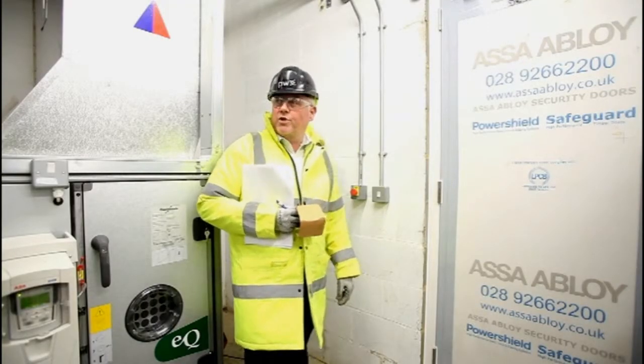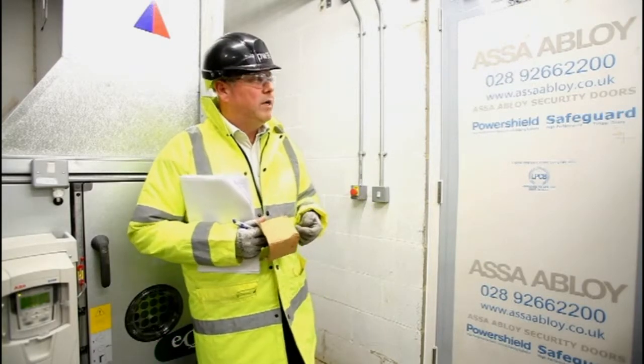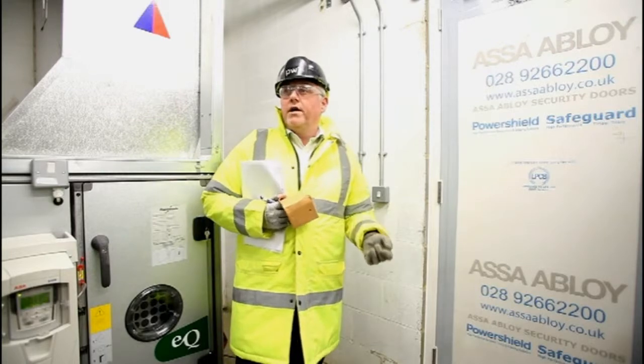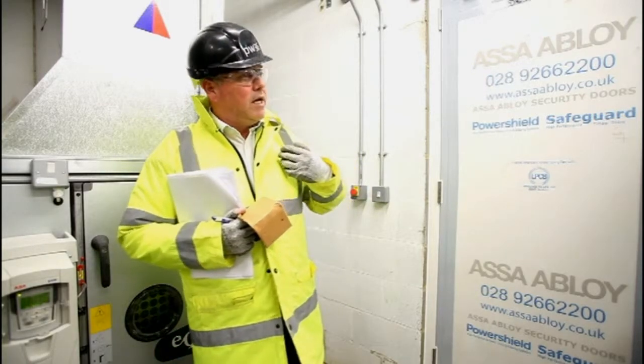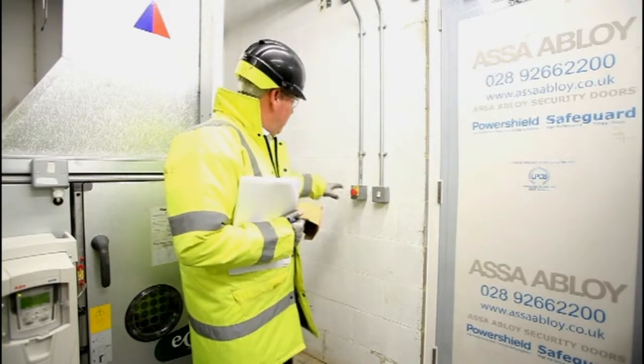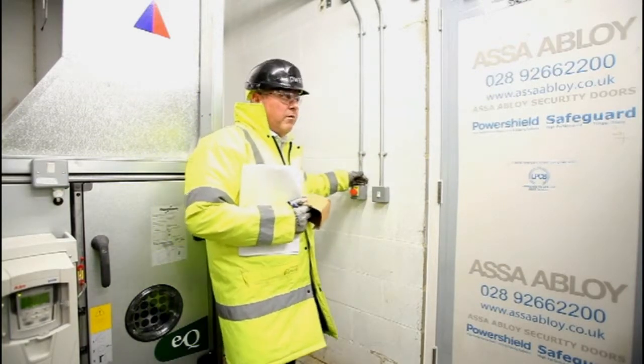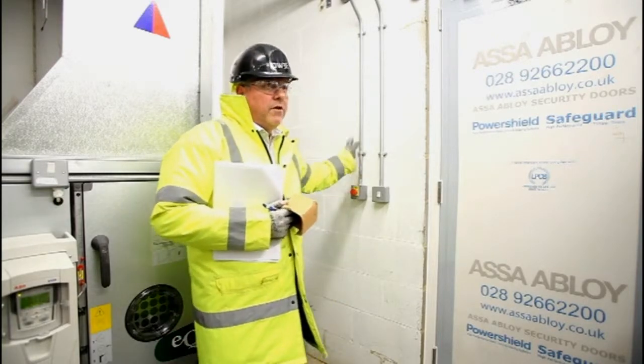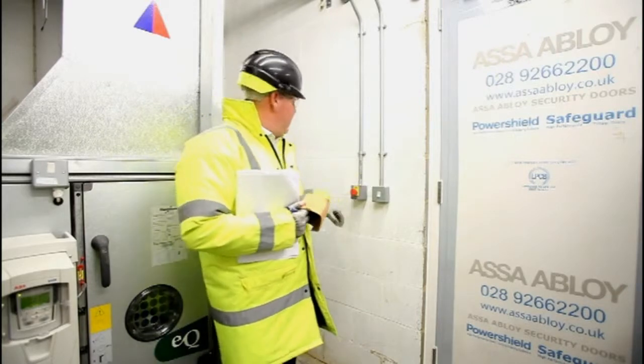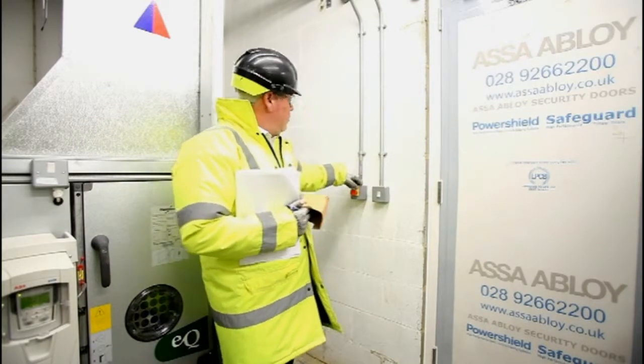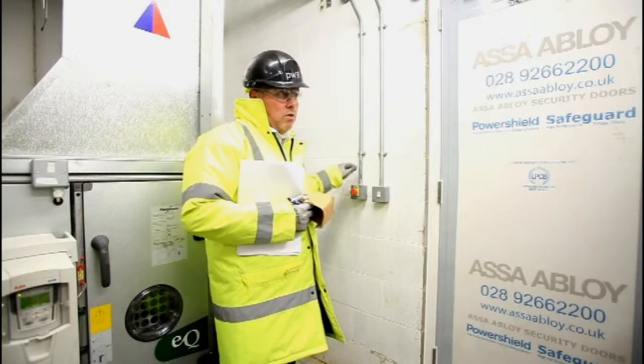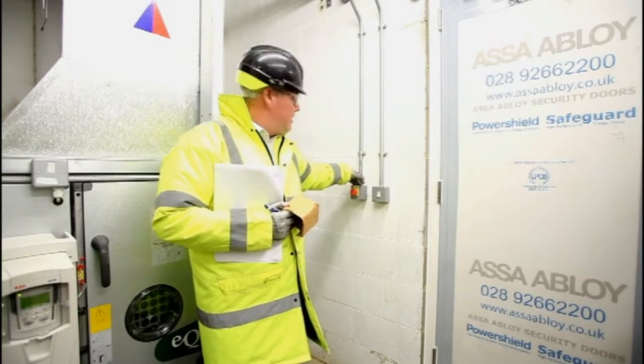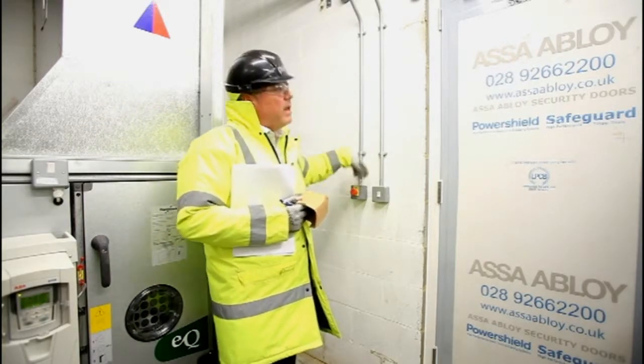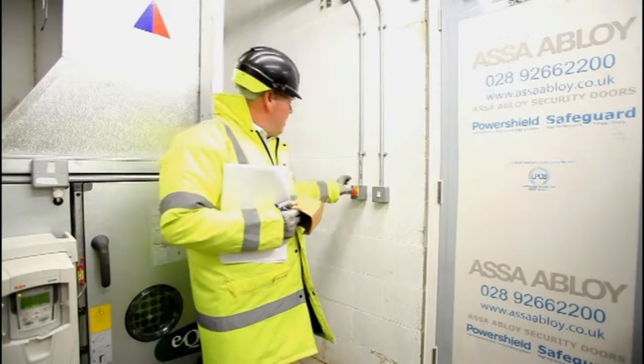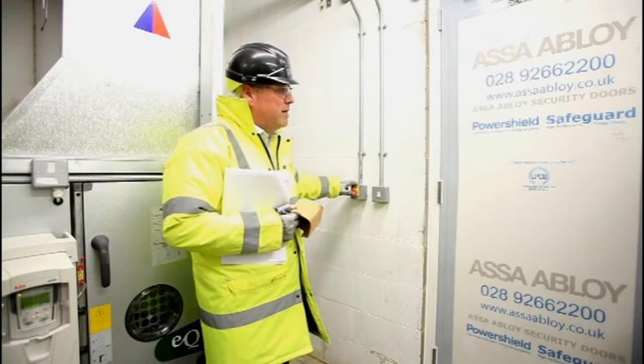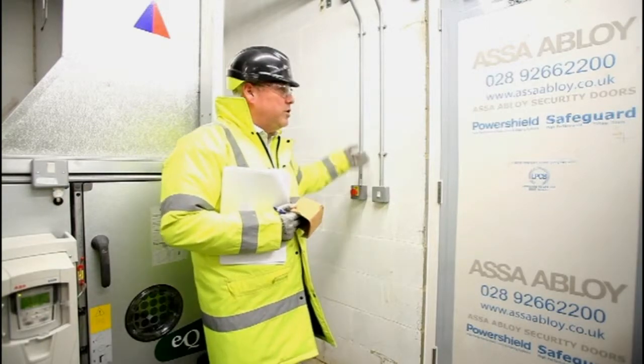There are several safety interlocks within the system that turn the system off should there be an issue. Should anybody be in the plant rooms and something become apparent, for instance there's a major leak or there's a fire, anything else, as you leave the plant room we have what we call an emergency knock-off button. This emergency knock-off button, should you knock that, will shut all the plant off in the space that we're in. Each plant area has an emergency knock-off button. Should there be 2 doors to the plant area, each door will have an emergency knock-off button. So should there be an incident, knock the button, turn the plant off. Should there be an incident where you need to reset it, you need to come back, pull the button out, re-energise the button. The BMS will take over and then put everything back into automatic.